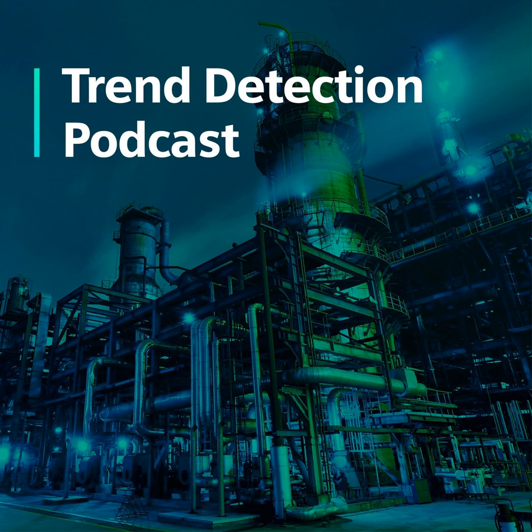To see how that impacts any data that you do have. Because that way, when you're starting off, you say, oh yeah, we've got current, we've got vibration, or we could install vibration, but we know that we run at different speeds, so we'll make sure we find a source for that data. Often variable speed drives will have it, or an operational SCADA system may have it. And so you just know what things you're considering.